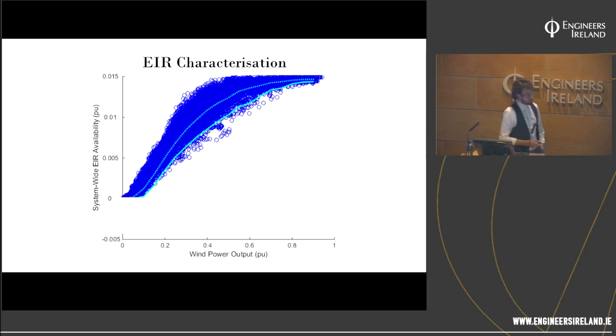I suppose you can see that when the wind power output of the system is low, you don't have many wind turbines online and above the power output that you need. Similarly, when the wind power output is very high on the system, you're pretty sure that most of them are online and above the wind speed that you need. It gets a bit hairier in the middle, because you can have lots of wind turbines online operating at a low speed, or you could have a low number of wind turbines operating at a high speed for the same system level wind power output. So if you're a system operator and you're seeing this, you could take the mean of that, and this is roughly what emulated inertial response capability I could get from the wind turbines as the system wind power increases.